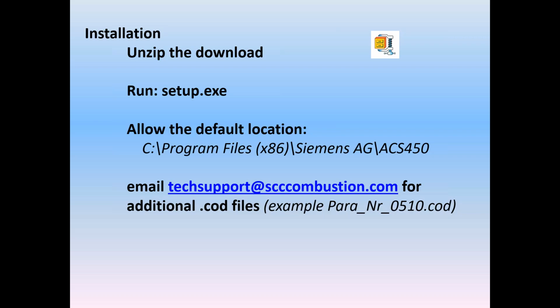All of these files throughout the entire history of the ACS and the LMV would be carried in the folder. So you're going to have about 20, 25 different COD files. Once you connect to an AZL, the LMV5 will automatically deduce what version you're running and format your reports according to the current COD file.